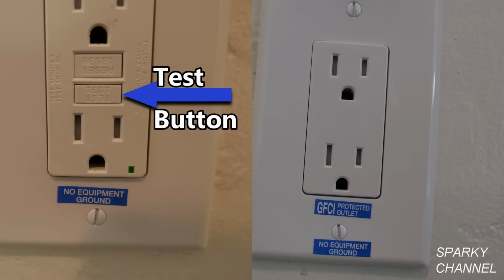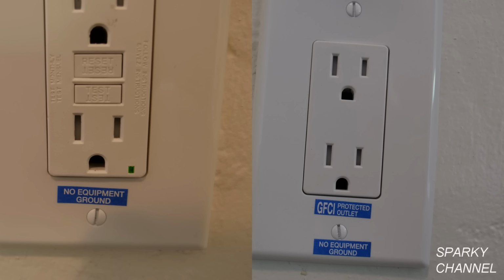Now, after testing to see that all of the downstream receptacles turn off after pressing the test button on the GFCI, I'll place stickers on the receptacle cover plates as outlined in the NEC. The GFCI receptacle gets a no equipment ground sticker, and the grounding receptacles get both a GFCI protected sticker and a no equipment ground sticker.